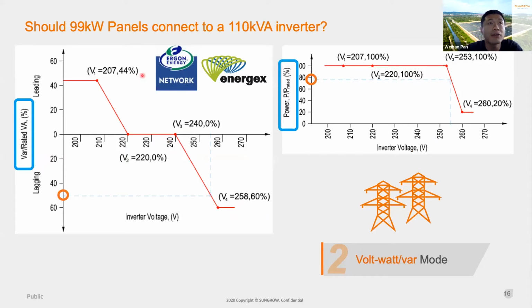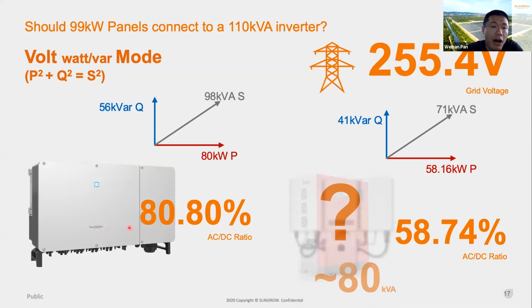best from Ergon Energy or Energex, they require the inverter to conduct the Volt-VAR and Volt-Watt mode, which means the inverter has to do the reactive control to compensate for the high voltage of the grid. For our inverter, for example, when the grid voltage is 255.4 volts, the reactive power is 56 kVAR, and the real active power is still 80 kilowatt.